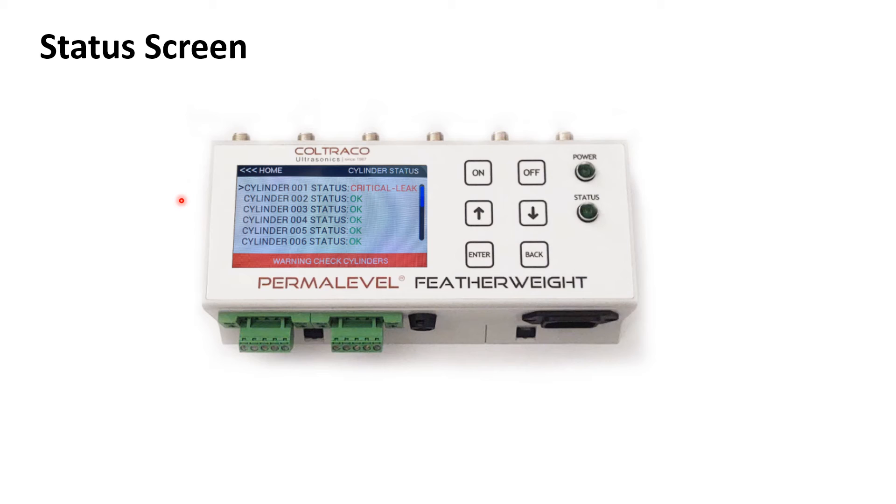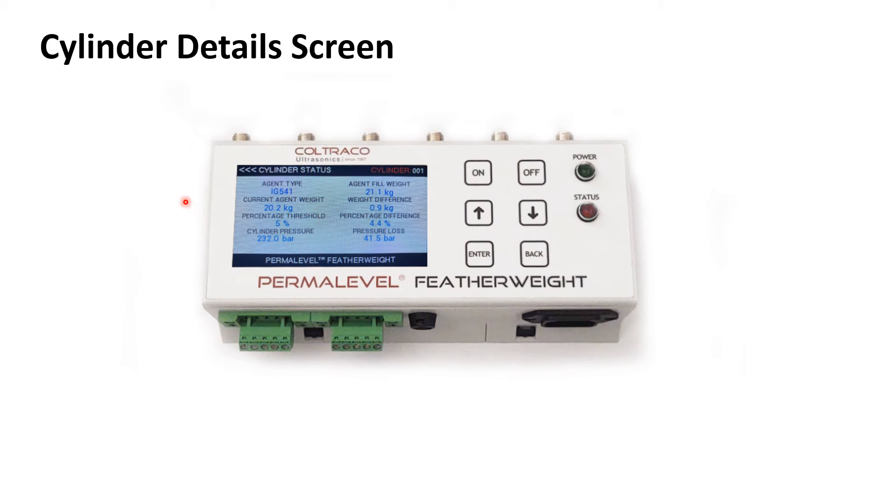If the user wants to view the actual status of that cylinder, they simply click enter on this cylinder, and then they will be presented with the cylinder details screen. On the cylinder details screen, it will tell you the agent type that's been used — in this case, we're looking at an Inergen IG541. It will tell you the current agent weight, the weight difference, the agent fill weight — the agent weight difference is the difference between those two — the percentage threshold that's been set, the percentage difference that that weight difference accounts to, the pressure loss, and the cylinder pressure.